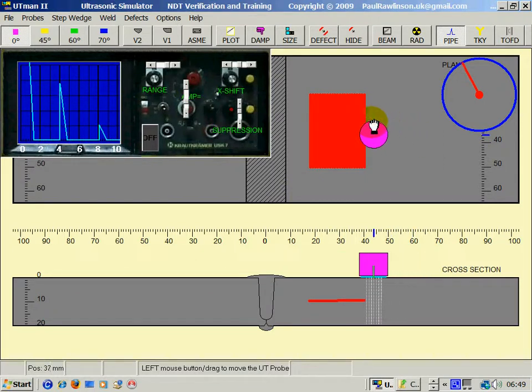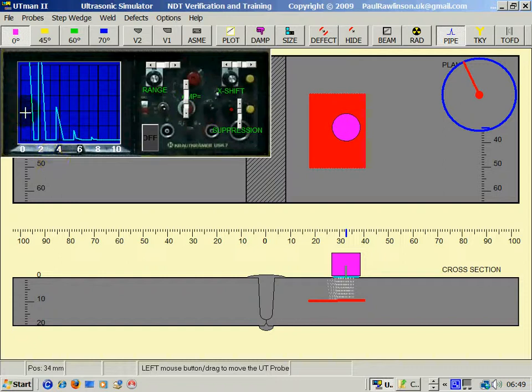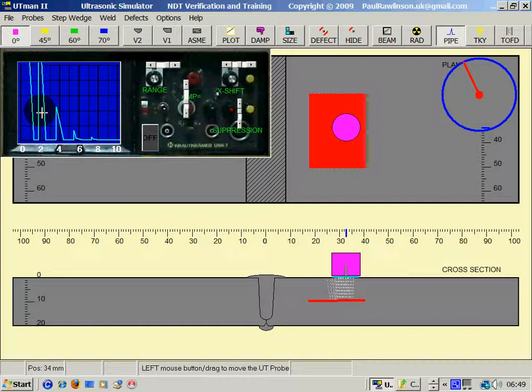We can measure the depth of the lamination on the UT screen. That's just coming in under 10, so about 9mm deep for the lamination.